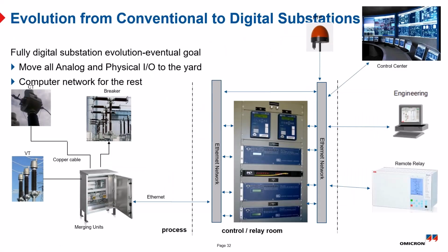So for a digital substation, to give you an idea what all that means, we've got a couple different iterations here. The first iteration is something called merging units. A merging unit is basically a fancy way of saying a digital relay out in a cubicle somewhere. It's going to measure the voltages and currents, read the breaker position, and issue trip and close commands as the system orders them. And it lives out in the cubicle. It's just going to be an aluminum box most of the time.